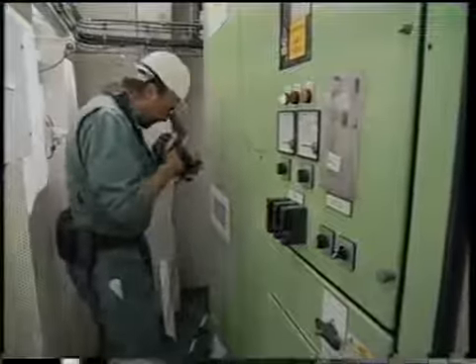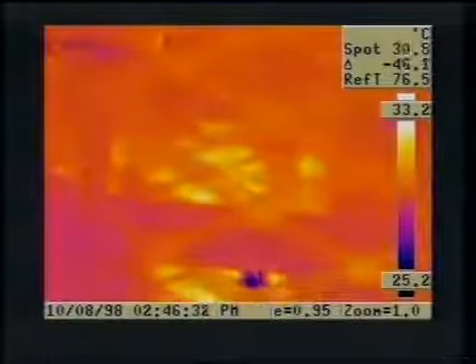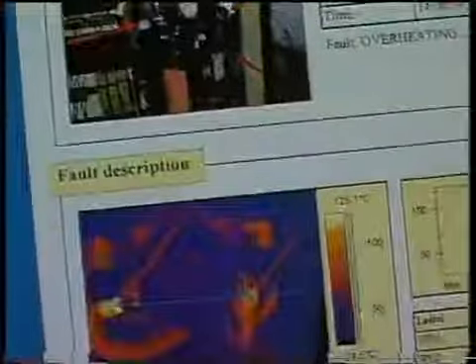A recent development is the introduction of special observation ports at the back of the high voltage cabinet to allow thermal observation without compromising safety. A digital stills camera provides a standard visual reference, and both kinds of image are incorporated in the contractor's report.